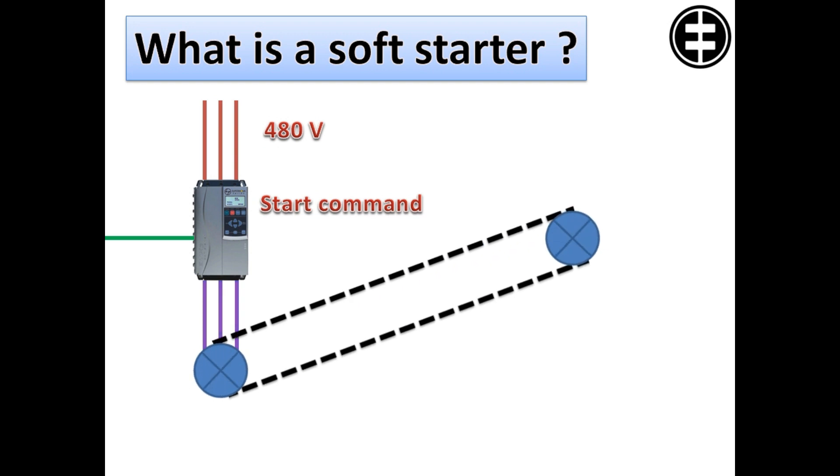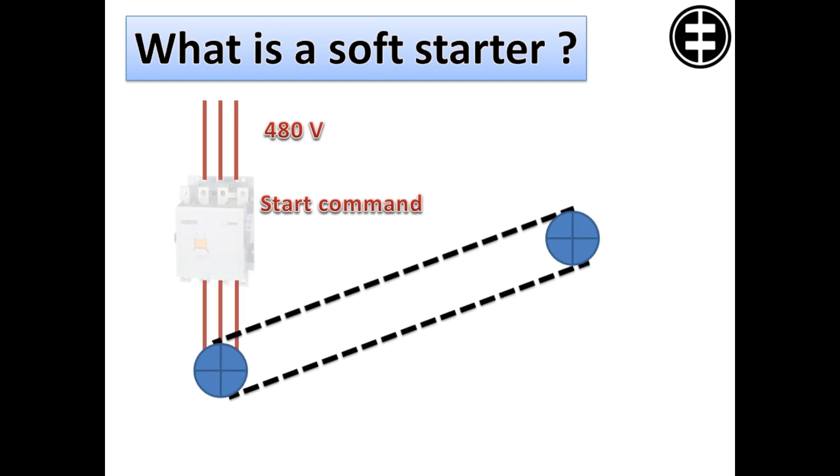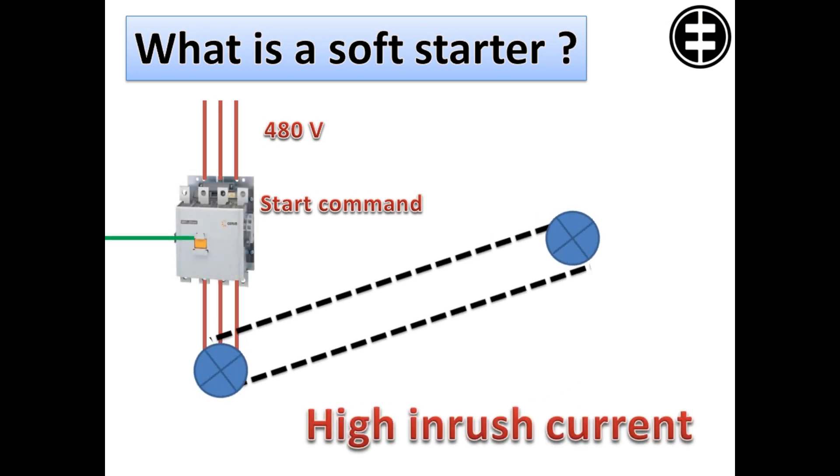Why is starting with full torque not preferable in some applications? Starting the motor with full torque makes it draw an excessive amount of inrush current, which can cause unwanted consequences like burning out the motor, wear and tear in the equipment and its mechanical parts, and increasing repair demand.